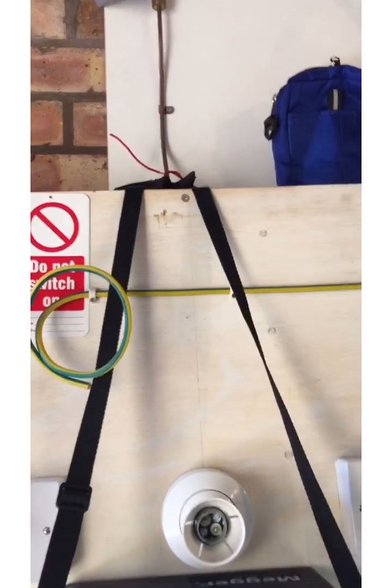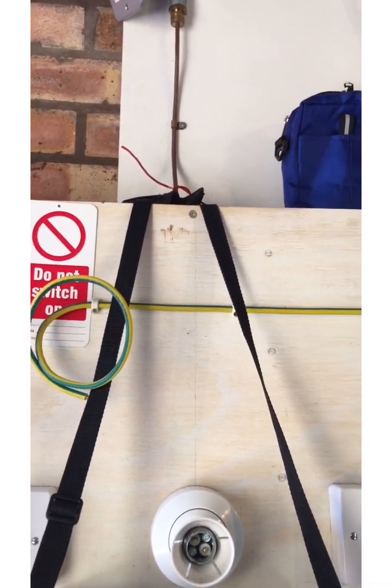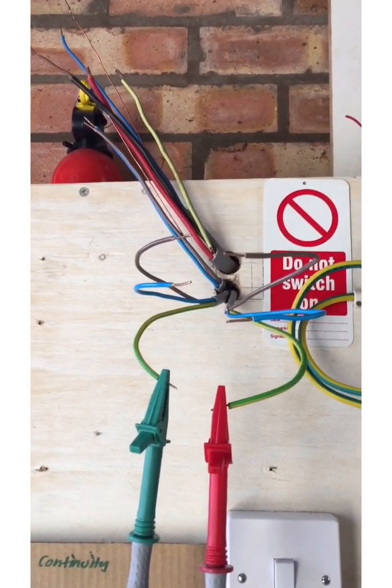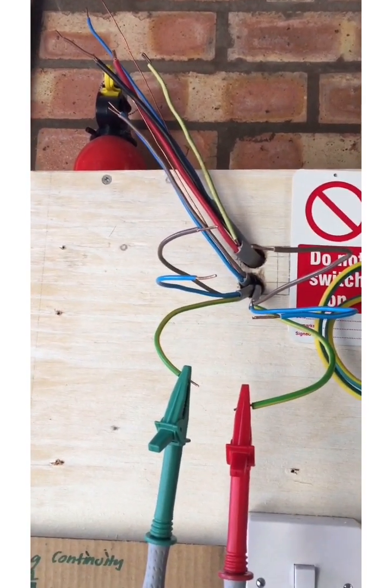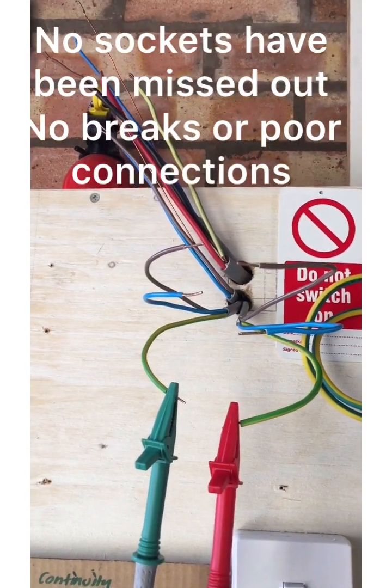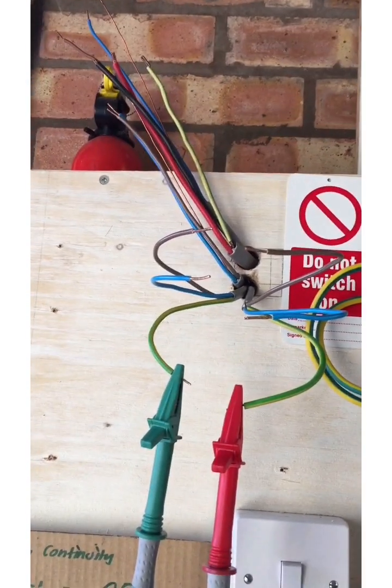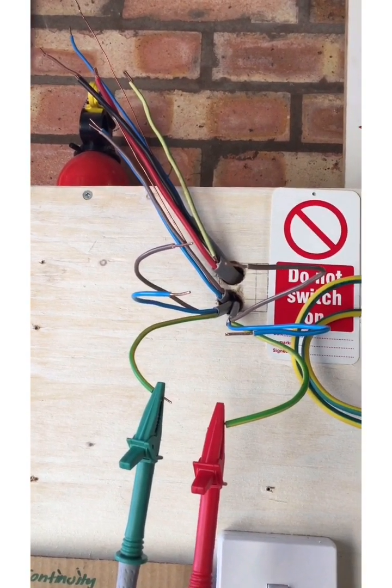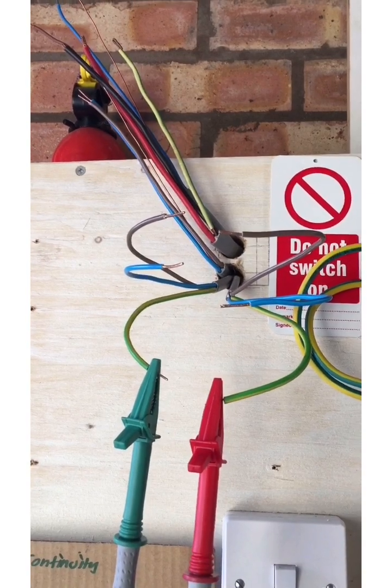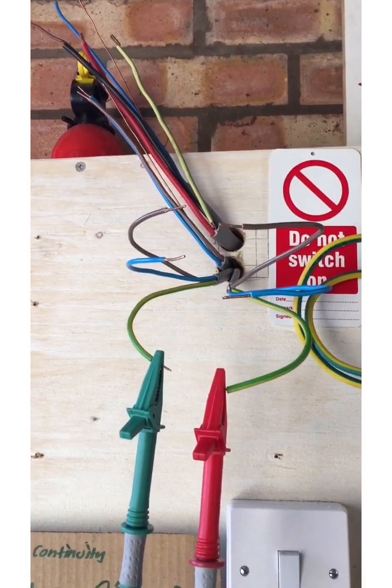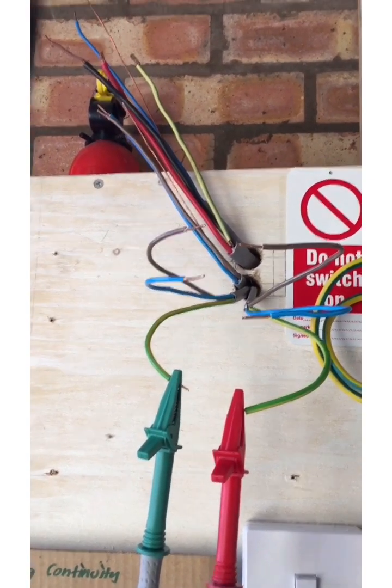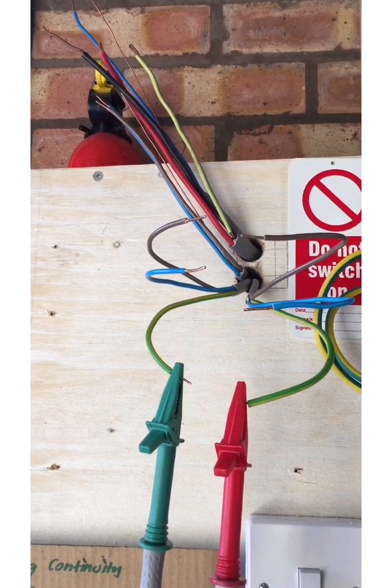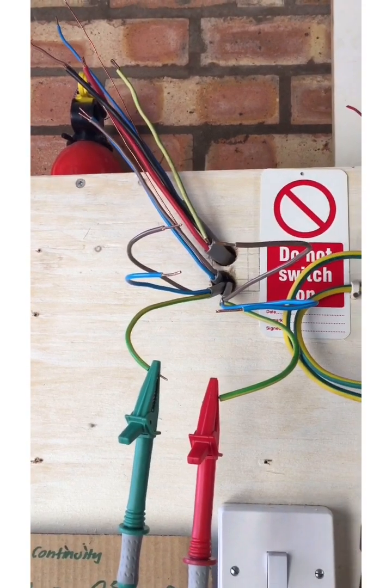So what that demonstrates to us is that those conductors there are continuously end-to-end. There's no breaks in the ring main. And also, something we're aware of is because the line and neutral are 2.5 millimeter squared and the CPC is 1.5, we expect a resistance difference between them. And for conductors at that size, we expect the CPC to be 1.67 times higher than the line or the neutral, which it is there or thereabouts.